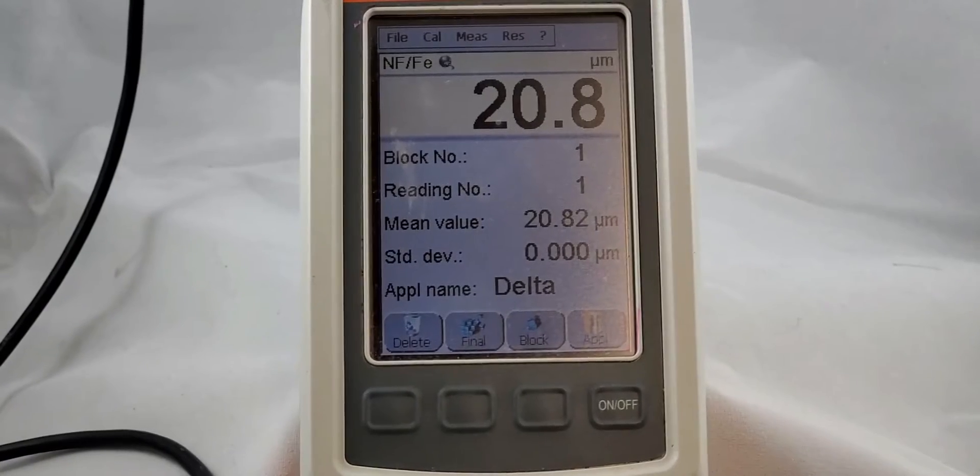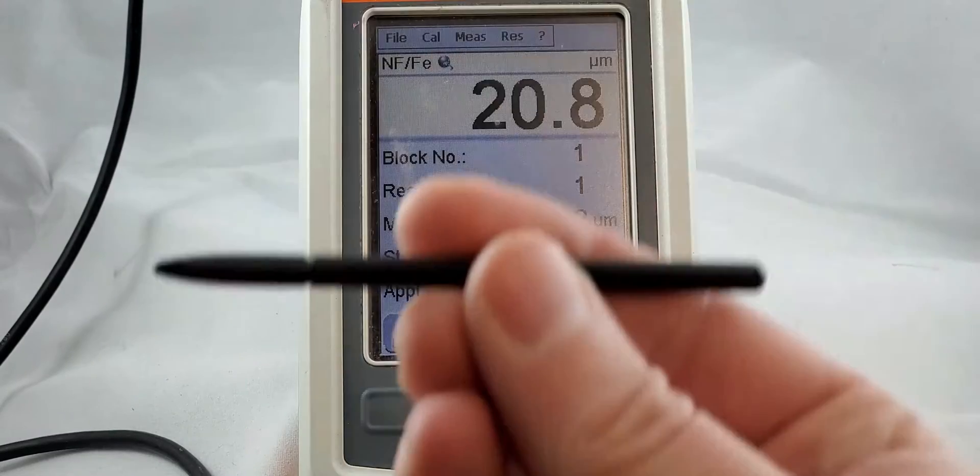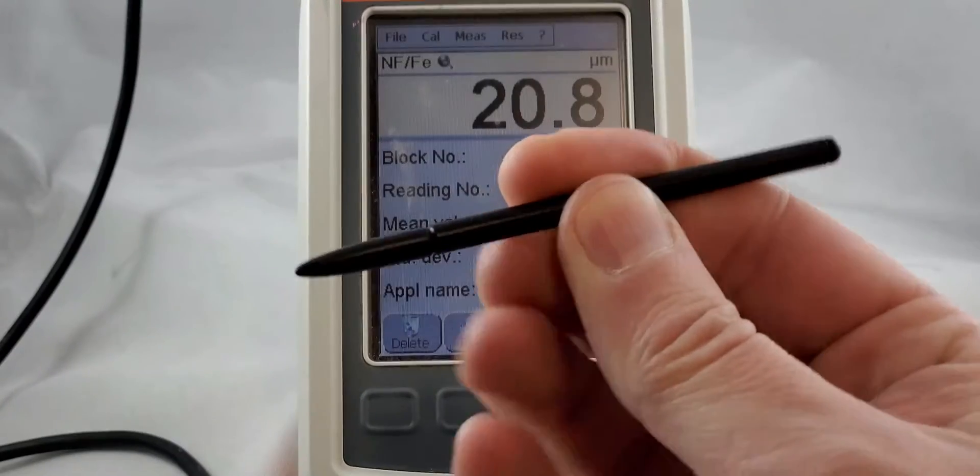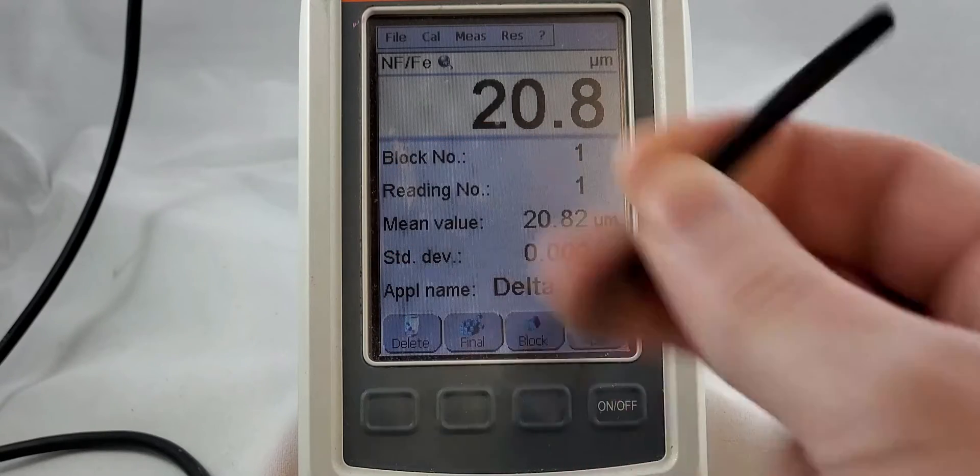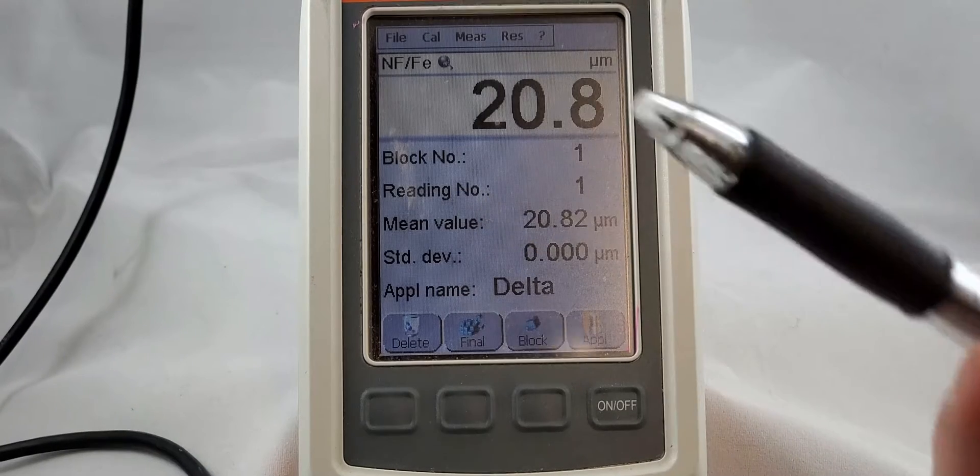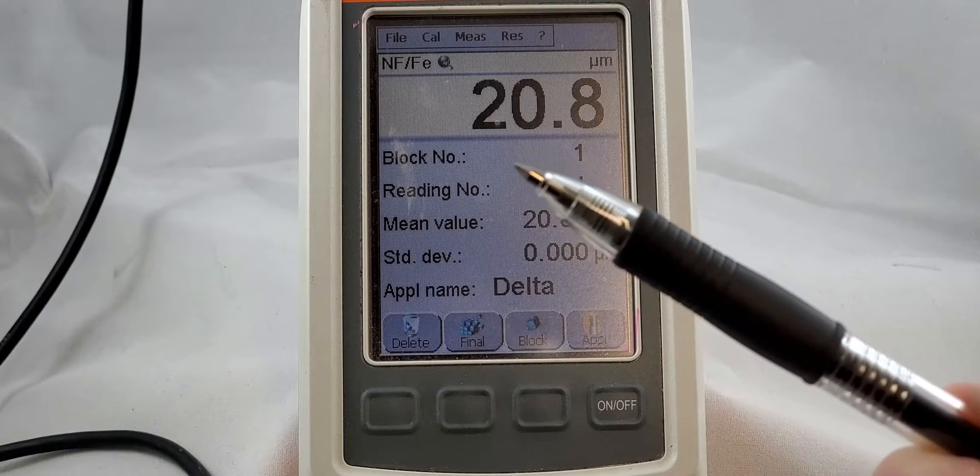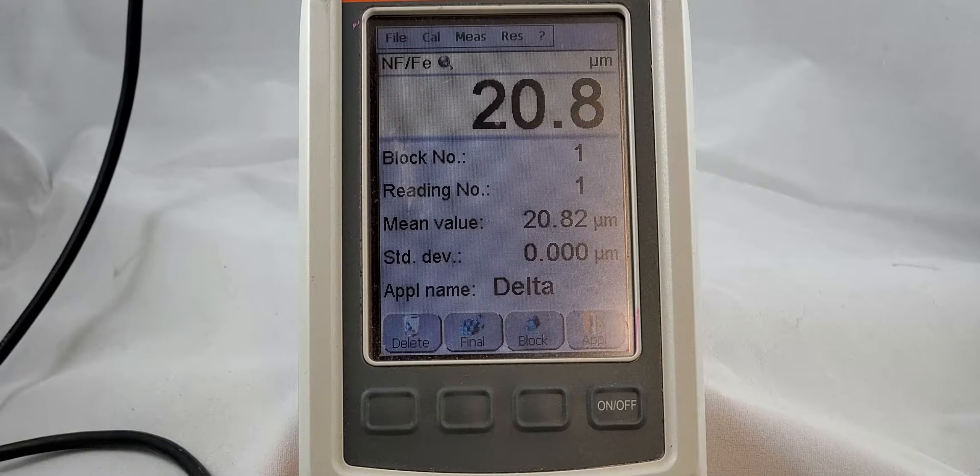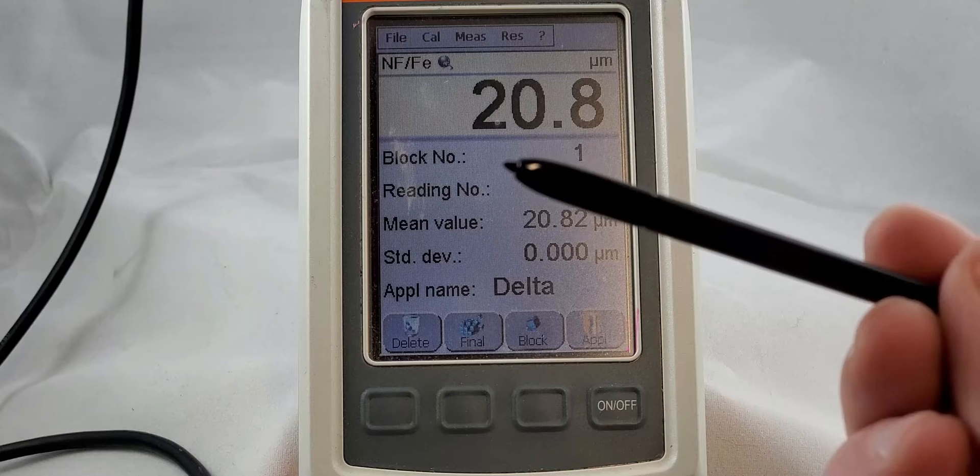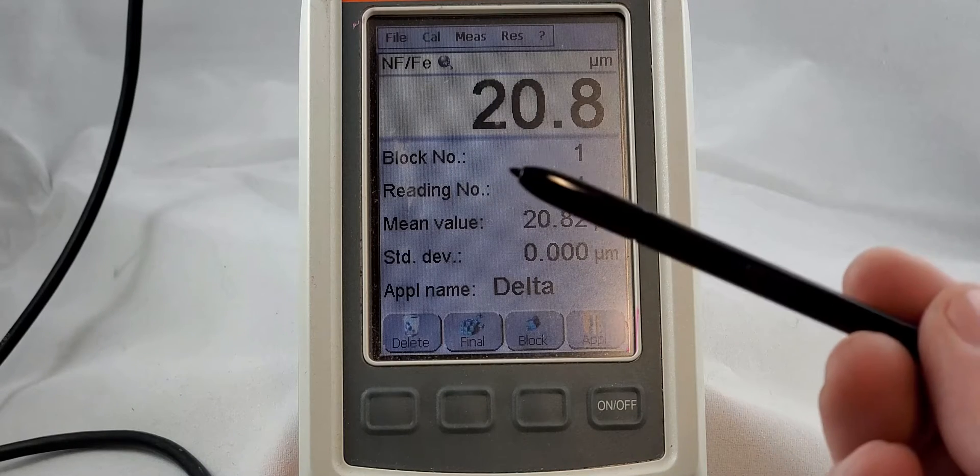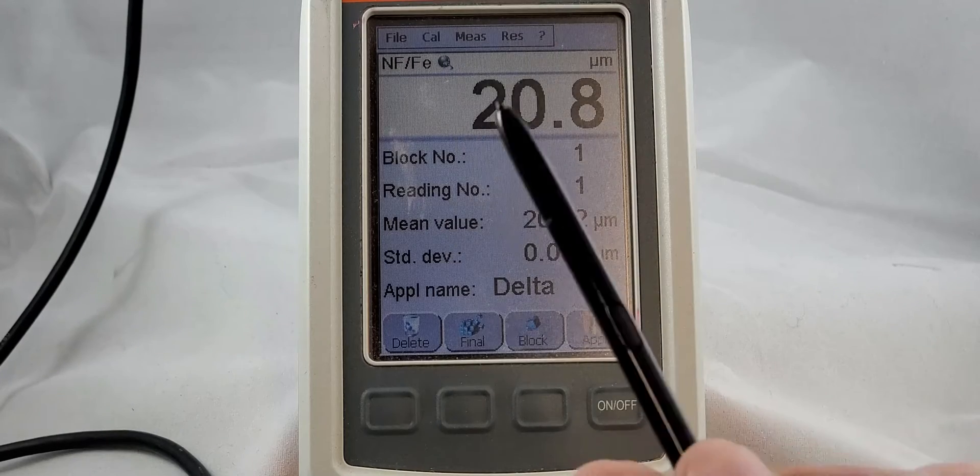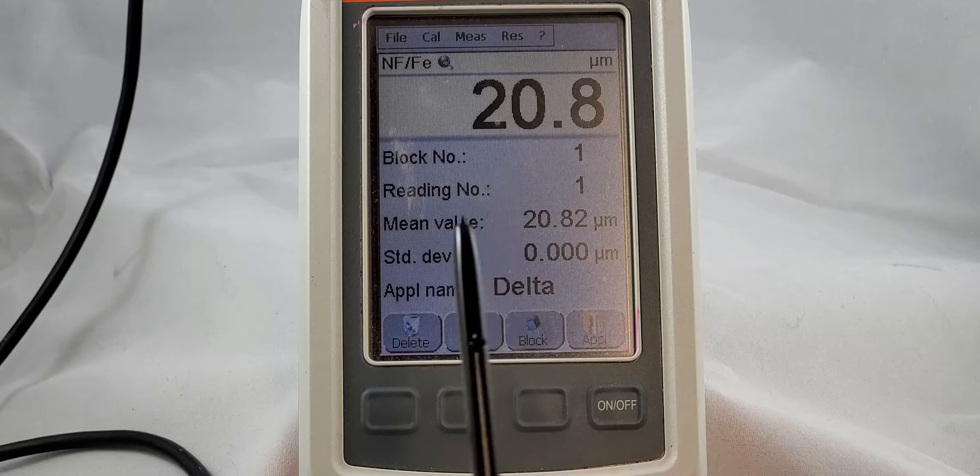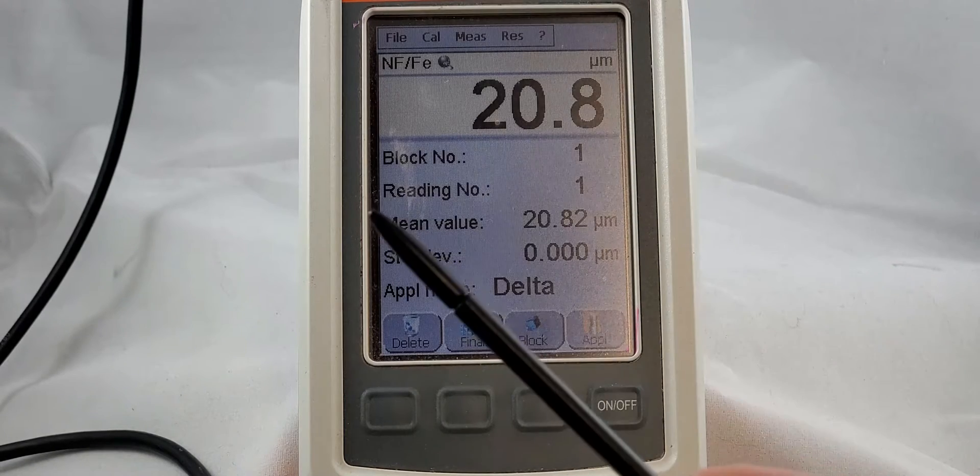We're going to start off by going to our calibrate menu. If you don't have a little stylus like this, I recommend either using a pen - obviously make sure that the point is retracted, you don't want to write on the screen. I have also had a lot of luck with the stylus out of my Samsung Note phone. I've also seen people use the Apple pen as well.